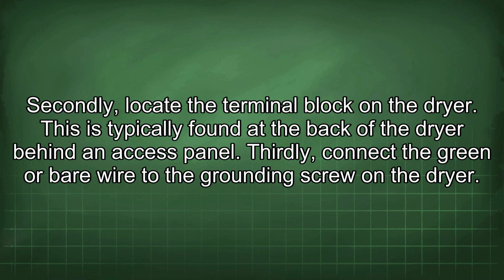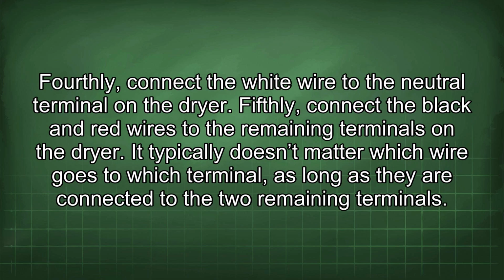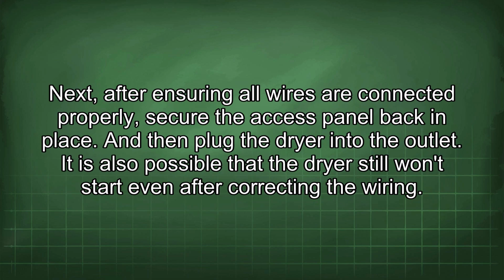Thirdly, connect the green or bare wire to the grounding screw on the dryer. Fourthly, connect the white wire to the neutral terminal on the dryer. Fifthly, connect the black and red wires to the remaining terminals on the dryer. It typically doesn't matter which wire goes to which terminal, as long as they are connected to the 2 remaining terminals. Next, after ensuring all wires are connected properly, secure the access panel back in place, and then plug the dryer into the outlet.